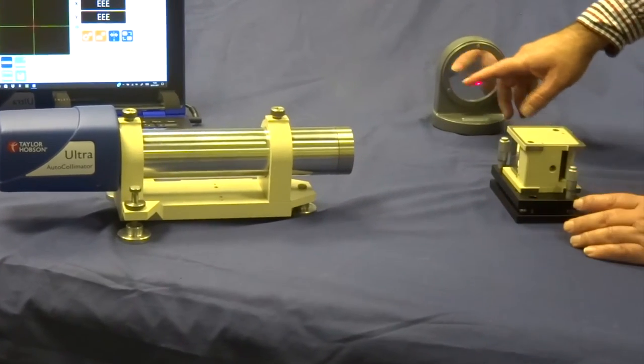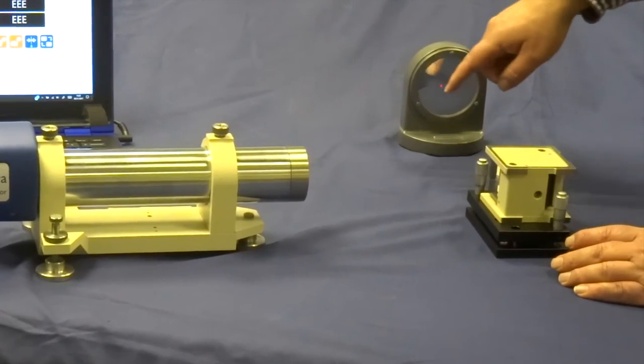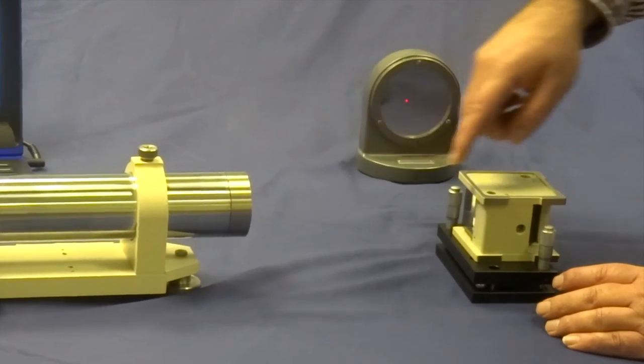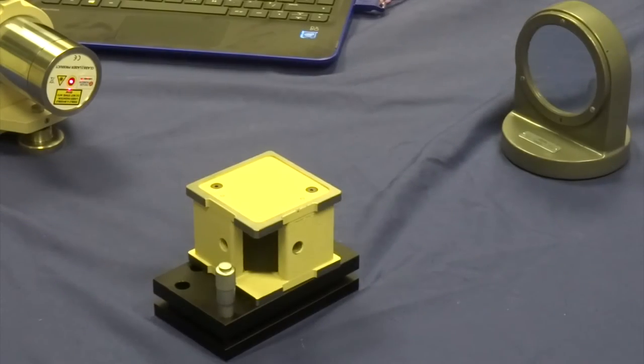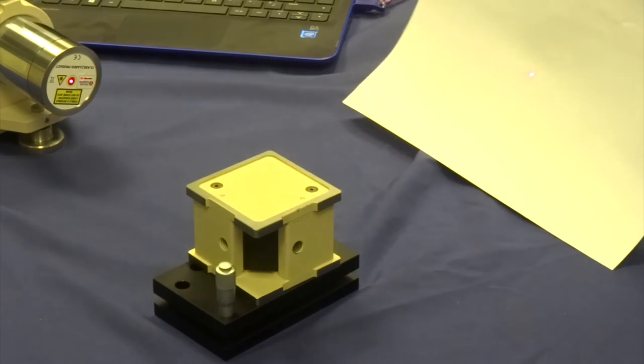We now need to square up the optical square front face to the autocollimator. I would block the main mirror on line two for this.